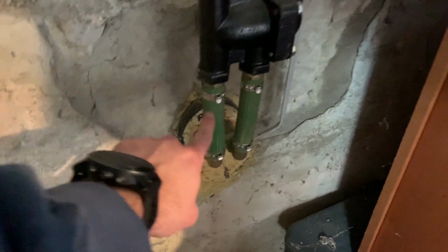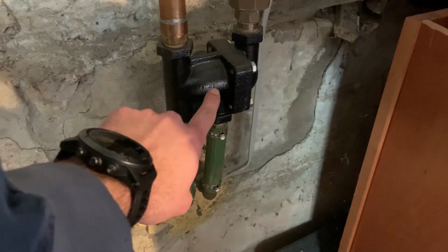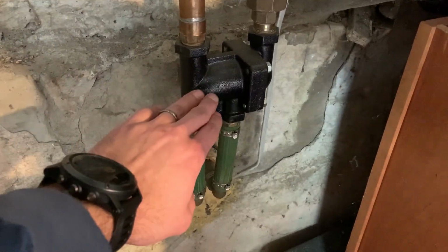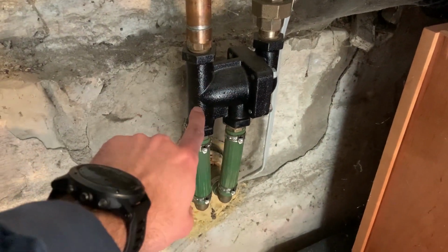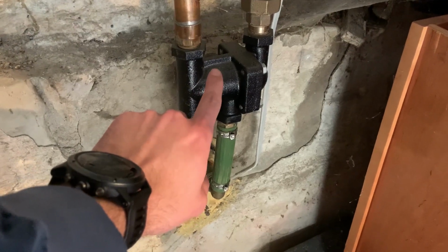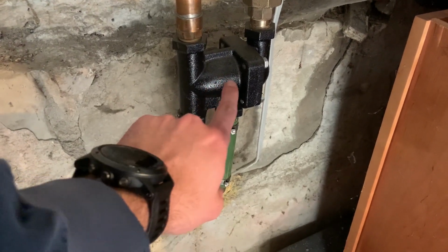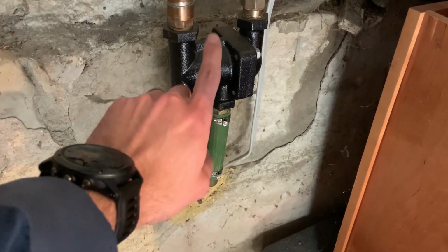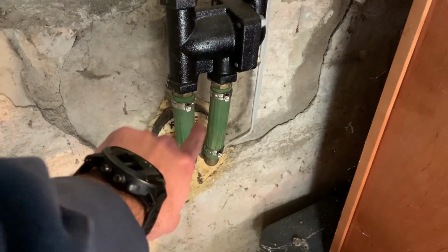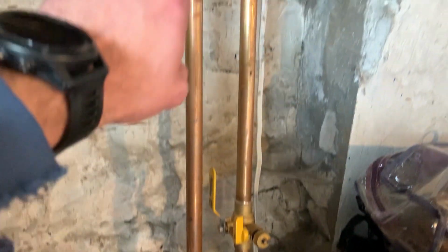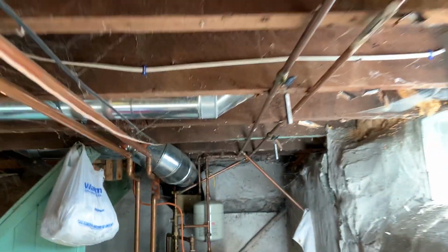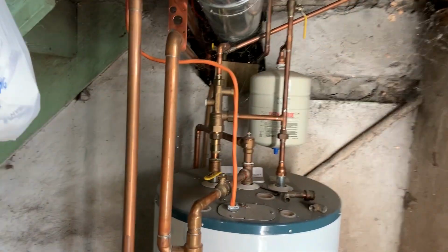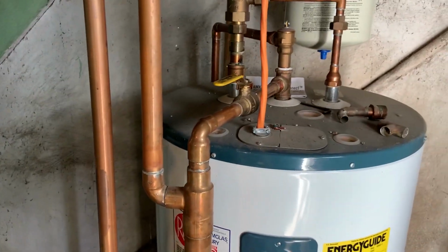So the hot water comes in this way, and this is what you call a thermostatic mixing valve. This thing does not open up until the water temperature reaches about 165 degrees, I think, or 160 degrees. If it's below that, it recirculates back to the furnace. If it's above that, it opens it up, comes up the pipe, around through, and comes into the system to heat the hot water.